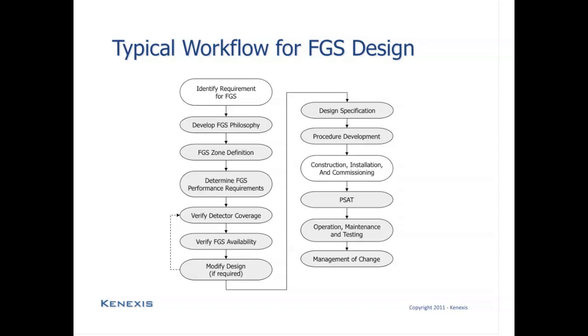After the fire and gas system philosophy has been developed, the next step in the recommended approach is to define the zones. Fire and gas systems are going to be broken into small areas or zones that are geographically limited, and also narrow down and define the specific actions that need to be taken and hazards that are present within a certain area. Zone definition is going to help in determining how systems are laid out, and they even go as far as to help first responders and other people that are responding to fire and gas situations to determine where the hazards exist and how to best address the hazards that have been realized.